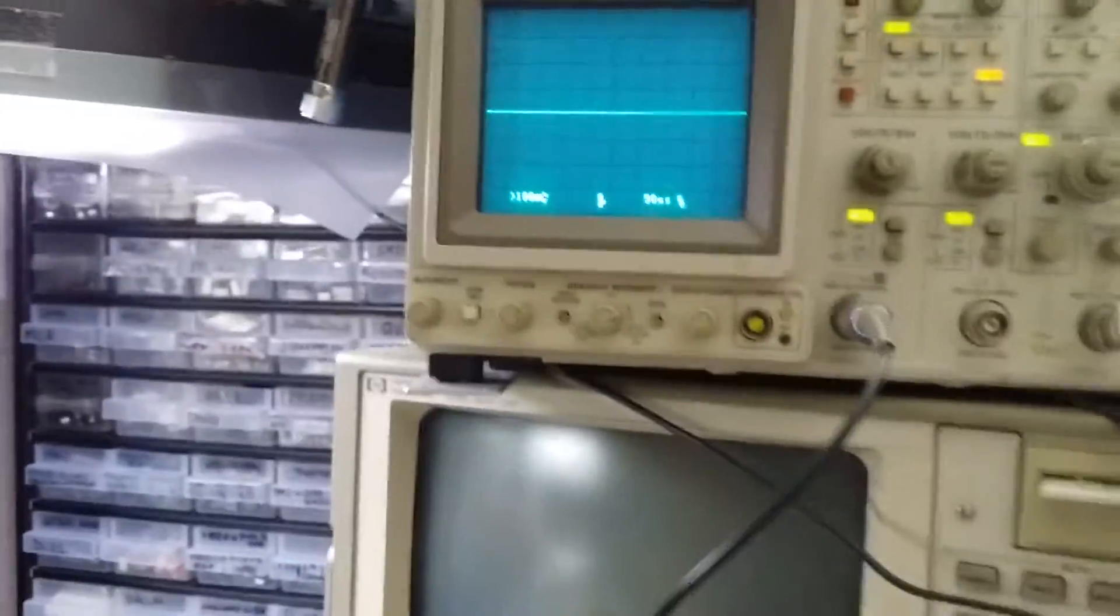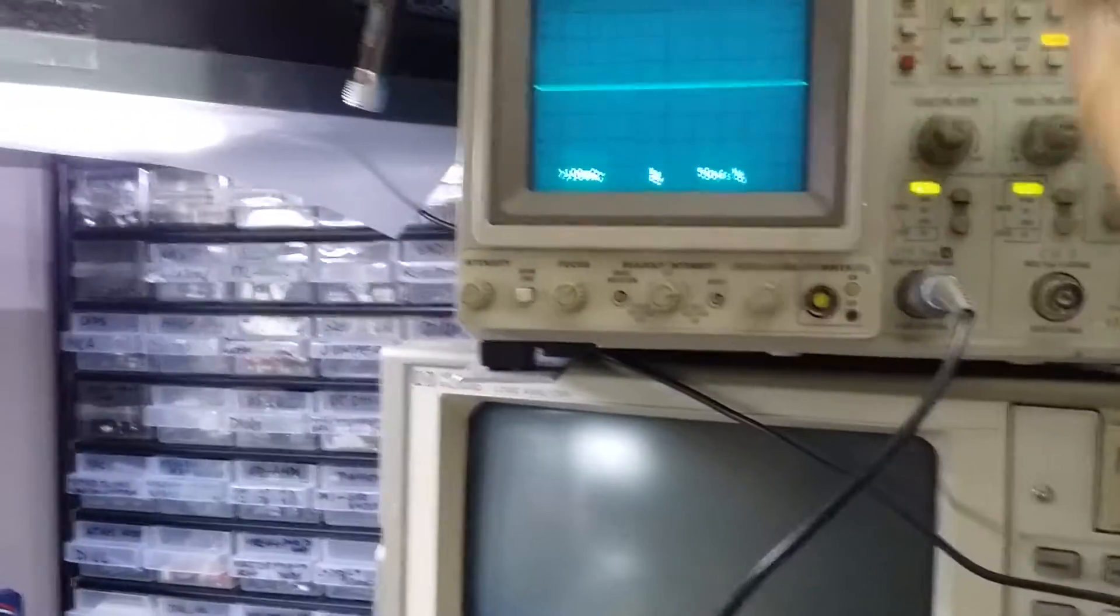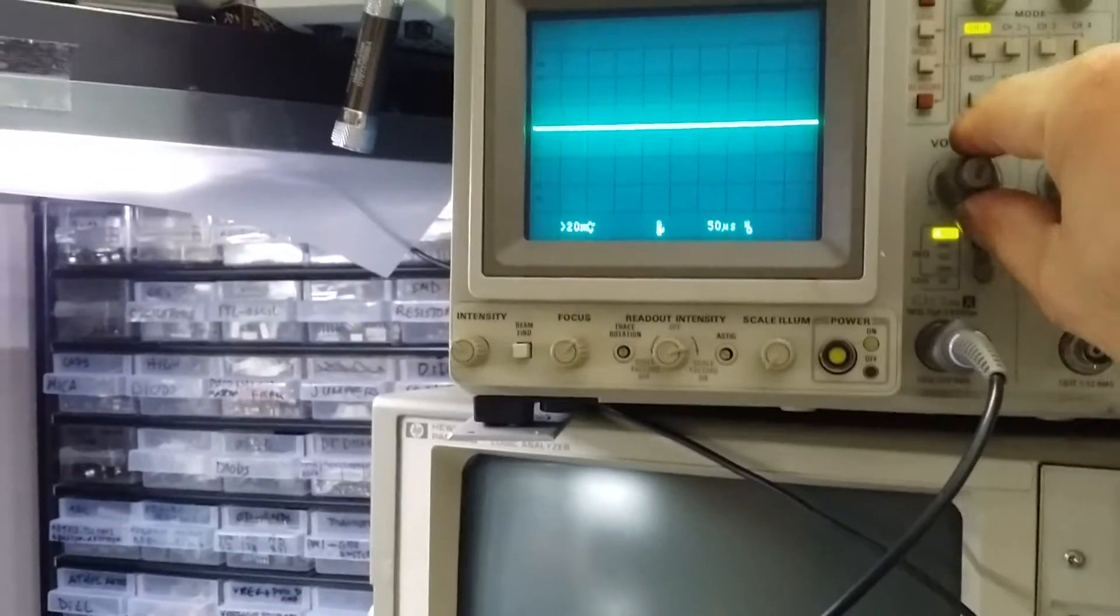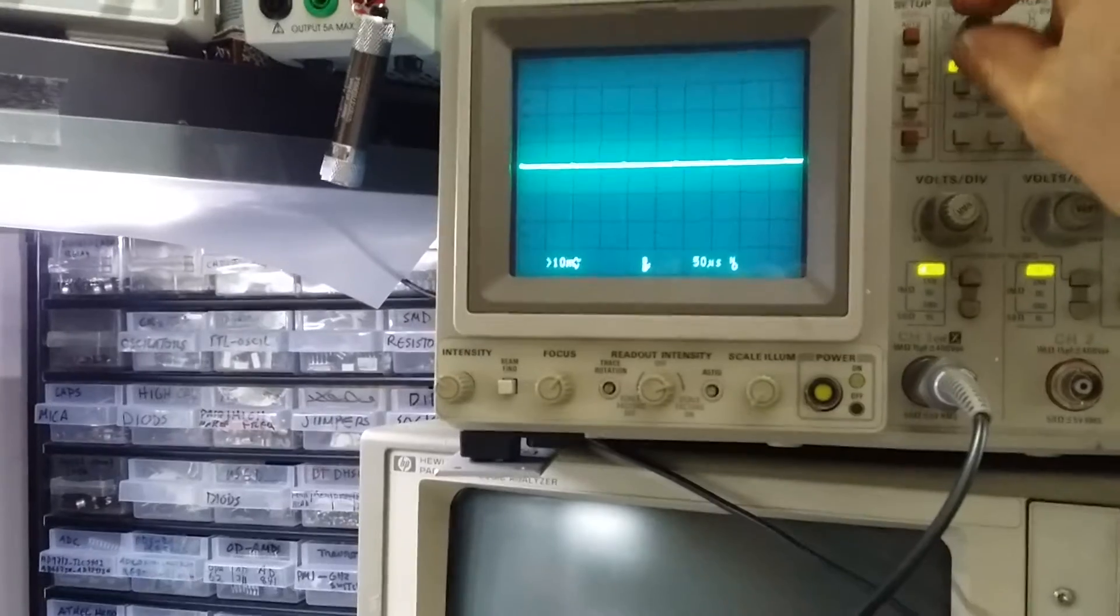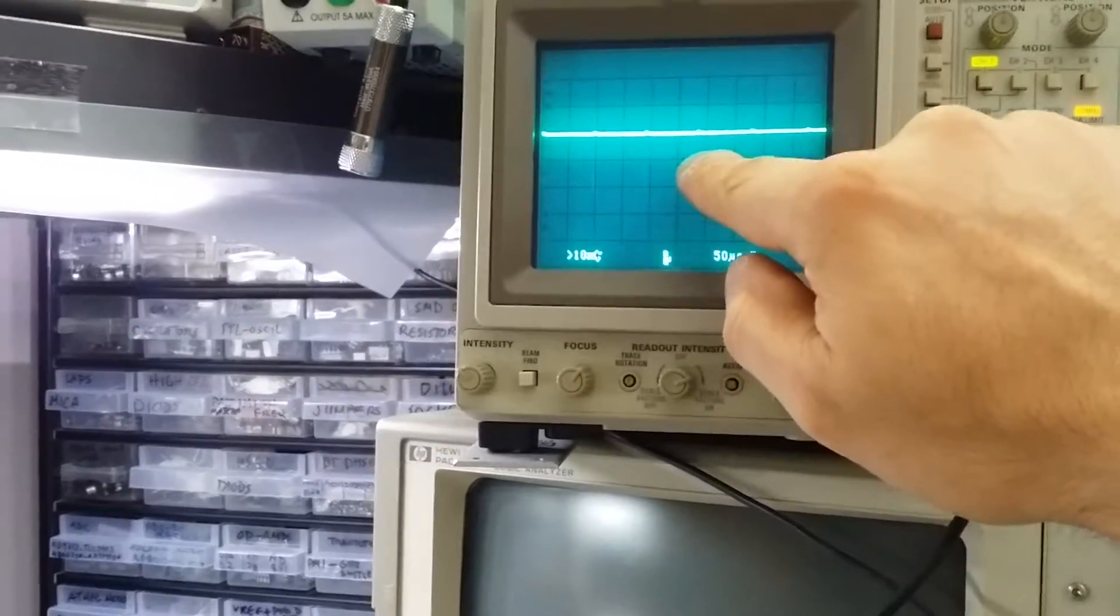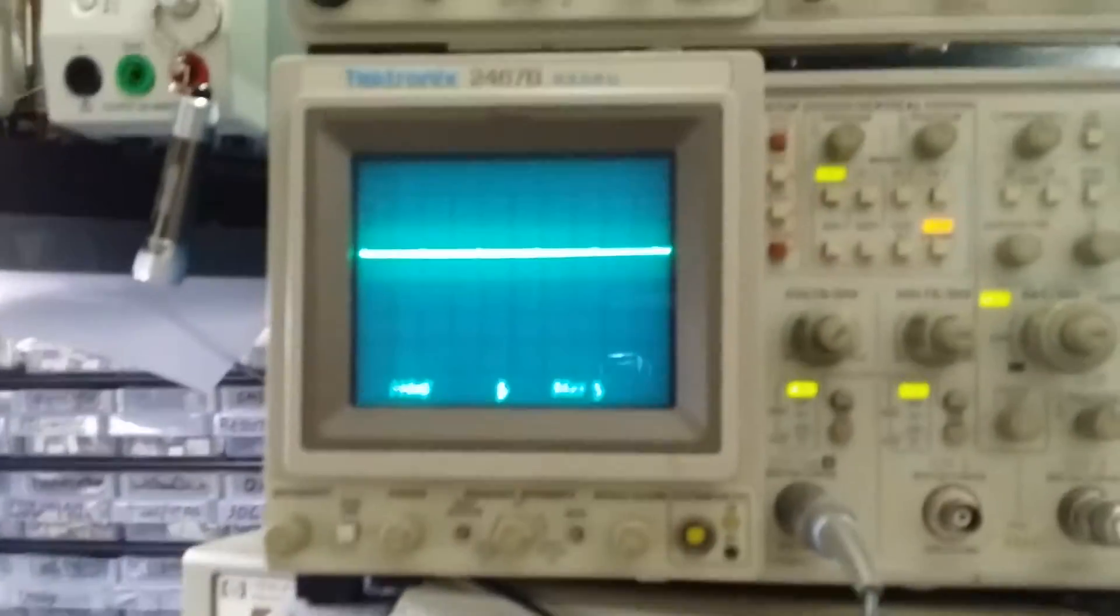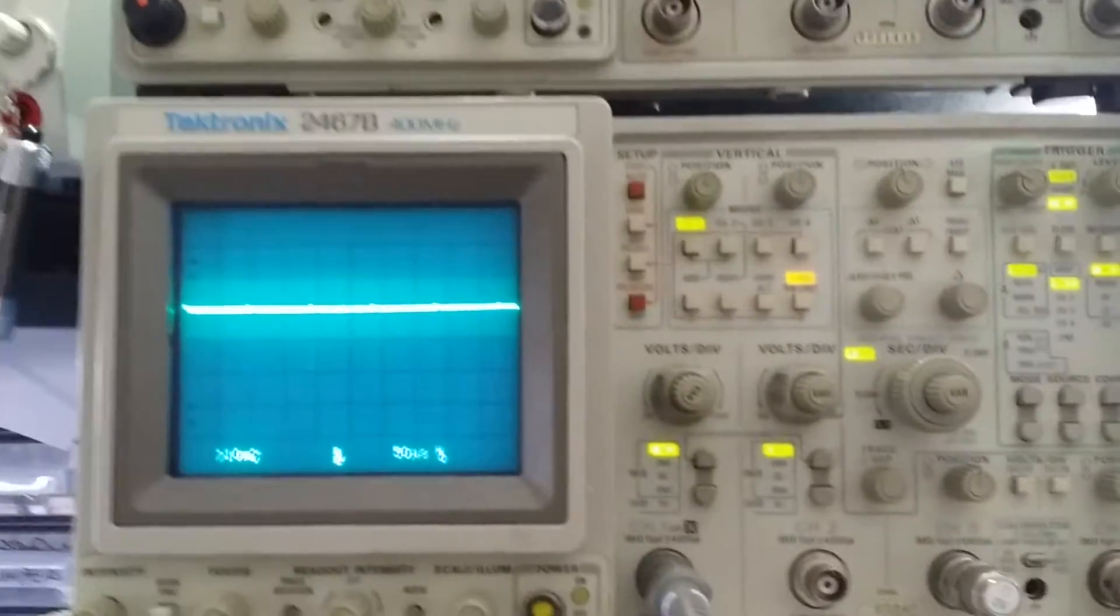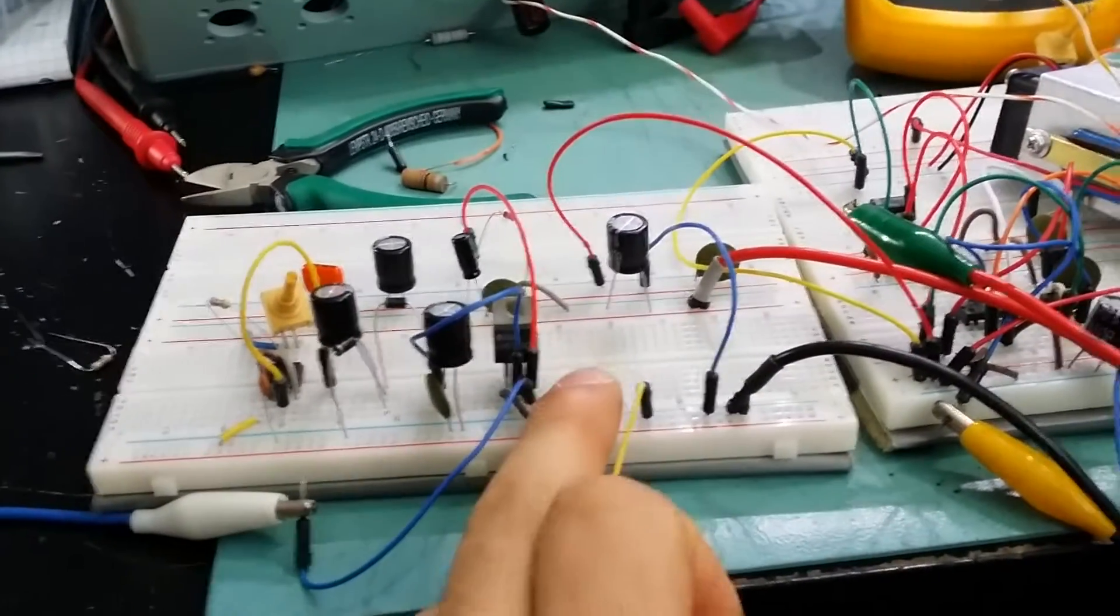So as you can see here on the scope, at the moment I've got the 20 megahertz limit on because if you're testing a power supply you need to have that on. And you can see here I'm on 10 millivolts per division, and I have about 20 millivolts of ripple.